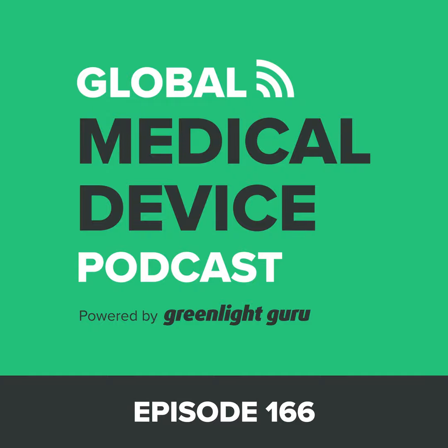Right. Which brings us to my last comment and suggestion about this particular guidance, Jon. And thank you for sharing your thoughts on this, because it's a good discussion that we're having here. FDA goes on to suggest that labeling be used to mitigate risk of possible skin reactions. Oh. And again, I find that particularly curious for a couple of reasons.